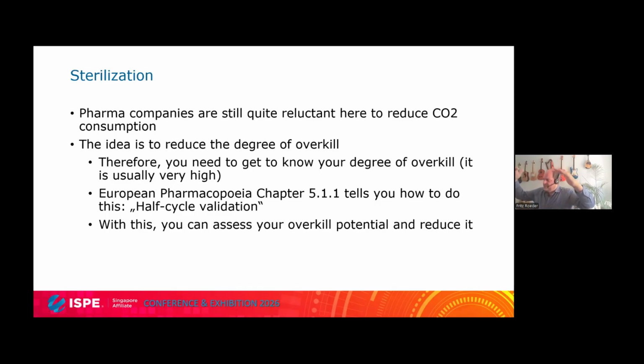Normally during sterilization validation, you apply a so-called full cycle, 15 at 121, 15 minutes. And then afterwards, you have put bioindicators in it, 1 million bacteria per bioindicator on a strip, or 2 million, something like that, and they should all be dead. But in this chapter, they talk about the half cycle validation. So you calculate based on some formulas that are shown in there. You conduct a half cycle of 7 minutes or something like that. And the question is then, how many bacteria are left?